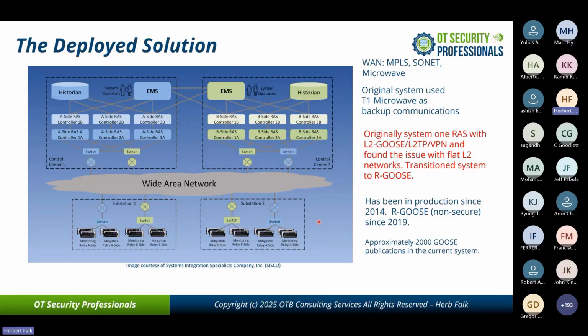And there are about 2,000 GOOSE publications going bi-directionally in this system. If you think about these controllers, they are huge GOOSE processors — they receive the 2,000 GOOSE messages, process them, run the protection algorithms, and then output results. To meet this 5 nines requirement, we decided to do a dual triple redundant active-active system.